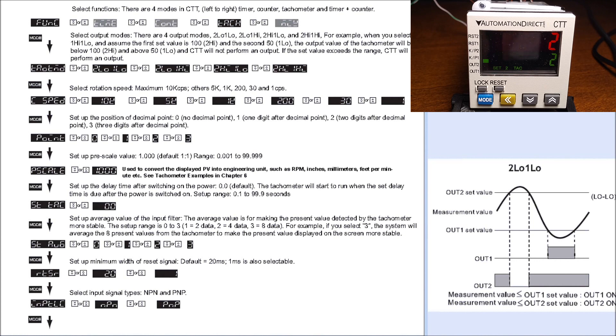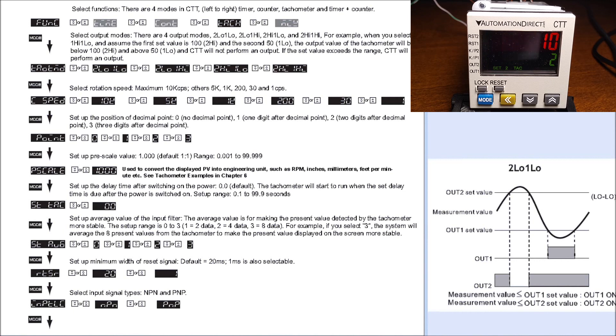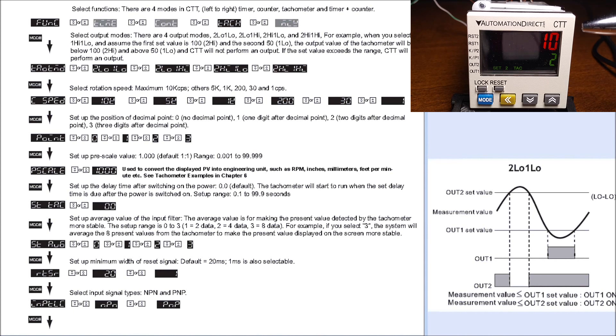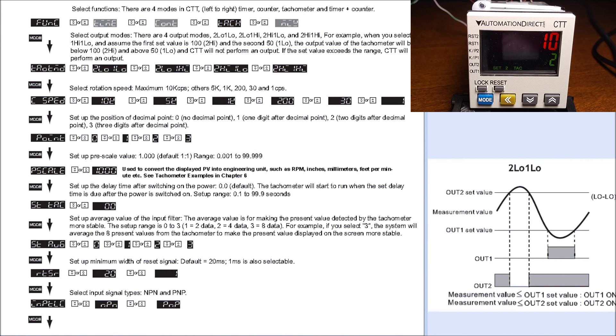Again, everything seems to be working fine. We'll turn that off. Now let's put a 100 milliseconds, or 10 times a second count into the unit and see what happens. Because we're averaging, you see it a little bit at 9, 10, now it finally settled on 10. This is why we do our averaging - there's 10 on our frequency, and you see now both of our outputs are now off.